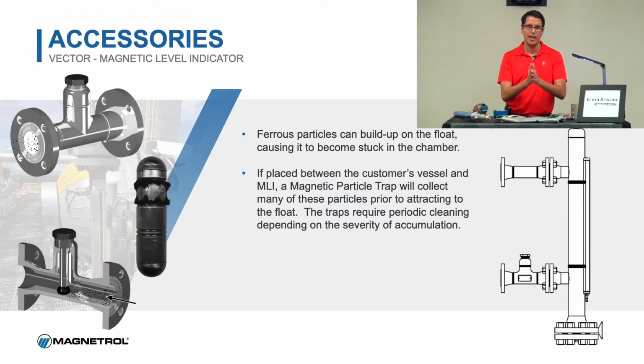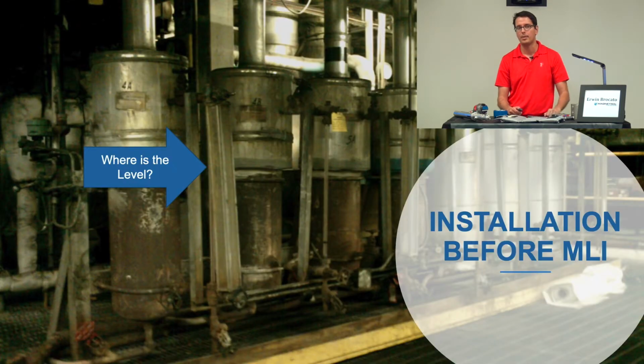So one of the solutions for that is what we call the magnetic particle trap, where you can see in the image right there, which is just a spool piece with a magnet inside of the spool piece that pretty much captures all that sediment, I like to call it, or filaments, over time. And you can open up the actual spool piece and take out the magnet and wipe it down. And that will prevent accumulation of the particles on the actual float. You only need one at the bottom process connection. You need to spool the top connection, of course, but you don't really need another mag trap on the top. You only need one at the bottom. Usually that's more than sufficient.